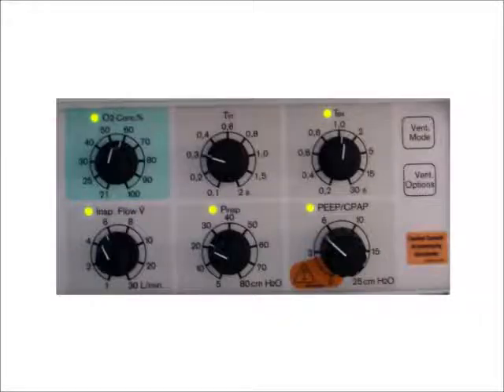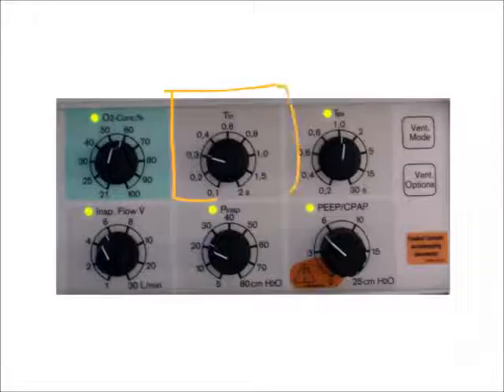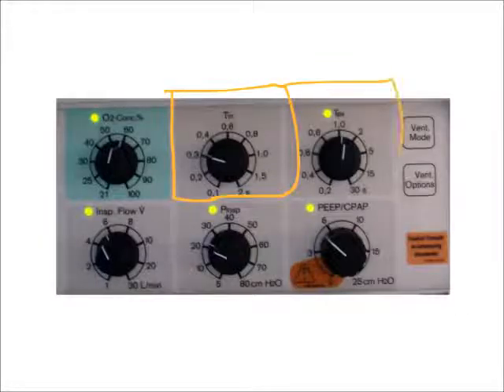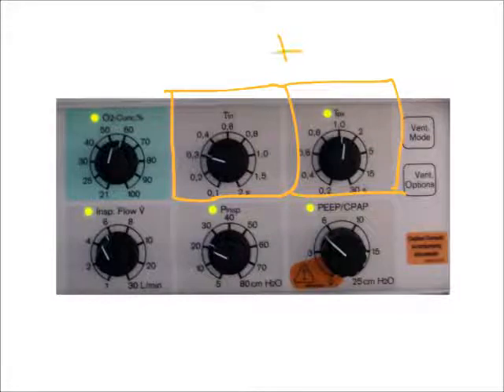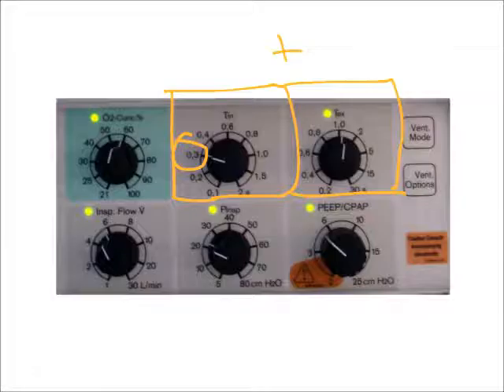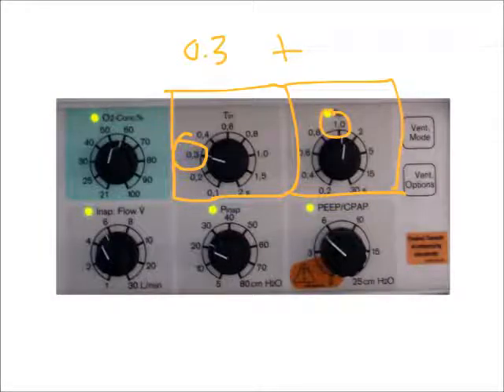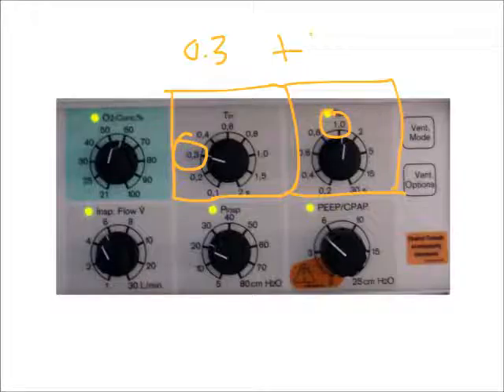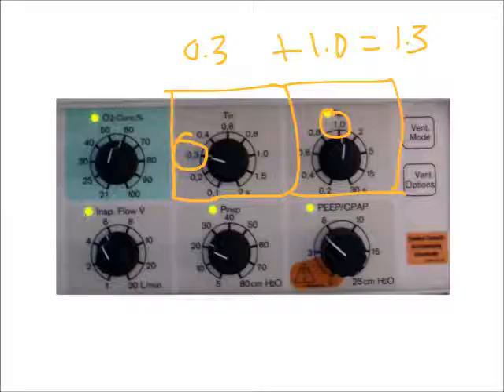Now in this older ventilator, this Baby Log, it's kind of easy to figure out my total cycle time using that equation because I have a setting here for my inspiratory time and my expiratory time. Based on this, if we look at the setting, I have 0.3 seconds plus right here it's set at one second. That equals 1.3 seconds, and that is my total cycle time.